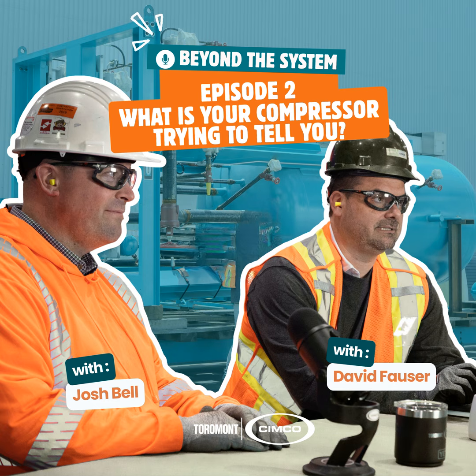That day when you come in and something isn't right, the people doing these inspections consistently are going to pick up on it based on the sound. It could be a rattle. If a belt broke off, you might smell the rubber burning. You might hear the belts flapping differently. I've been on service calls where a motor's come loose and moved forward and all the belts are loose. So hearing is a great sense to use, your sight, your sound, and even your smell. If you had a small ammonia leak, you're going to smell it. So I'd be keeping my eye out for those as well.